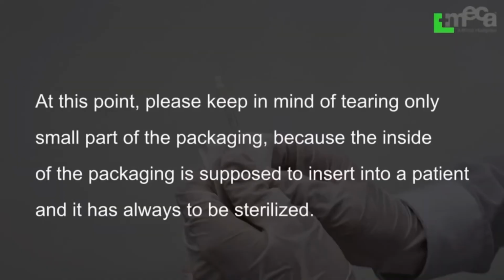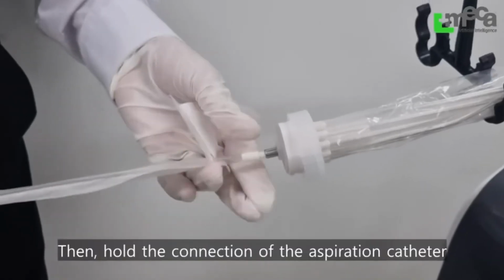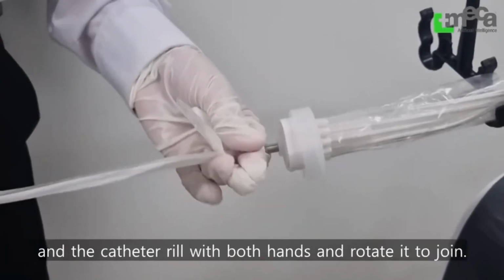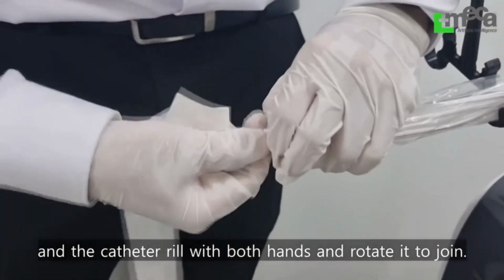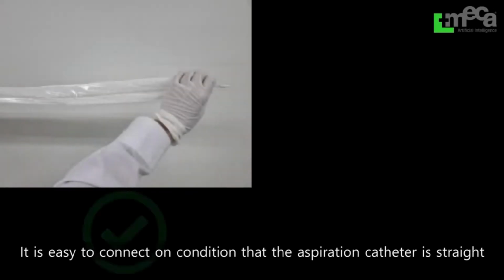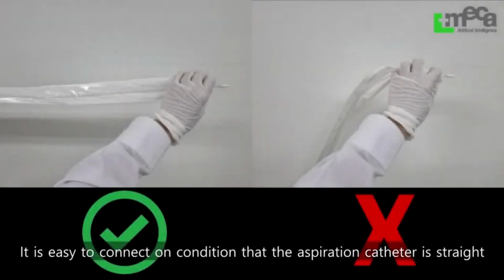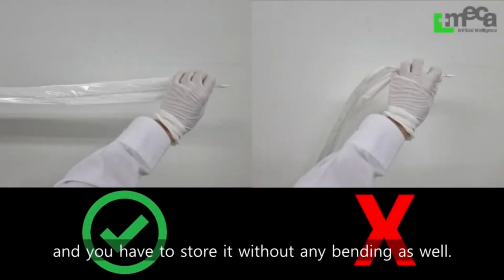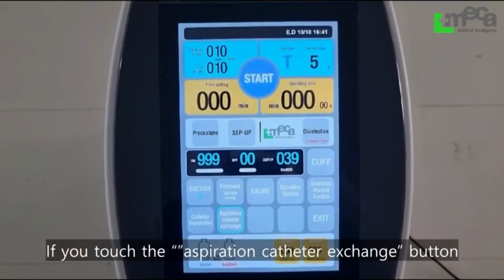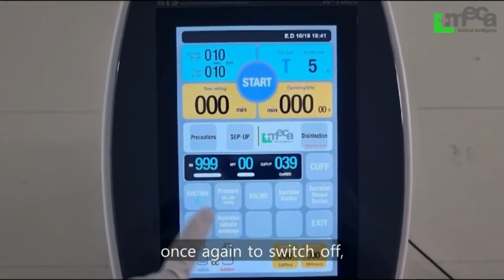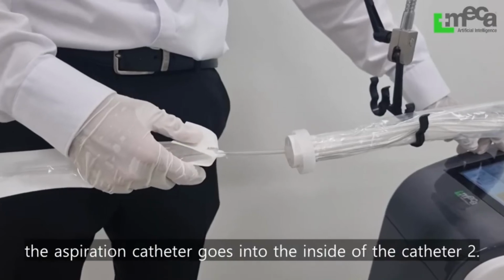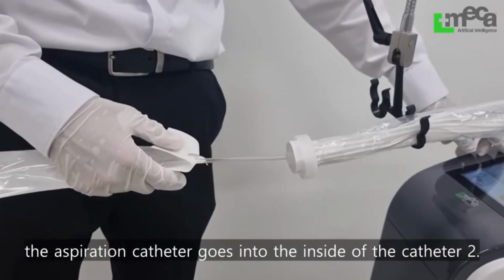At this point, please keep in mind to tear only a small part of the packaging, because the inside of the packaging is supposed to be inserted into a patient, and it has always to be sterilized. Then, hold the connection of the aspiration catheter and the catheter reel with both hands and rotate it to join. It is easy to connect on condition that the aspiration catheter is straight, and you have to store it without any bending, as well. If you touch the aspiration catheter exchange button once again to switch off, the aspiration catheter goes into the inside of the catheter 2.